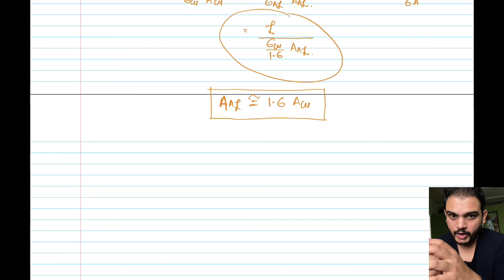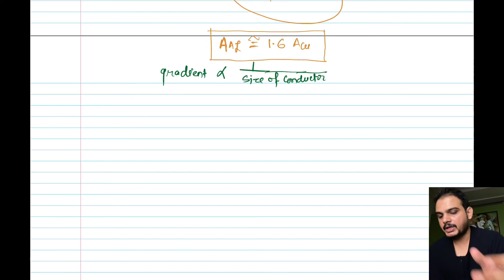This is advantageous because, as I said, gradient is inversely proportional to the size of the conductor. So if the size of the conductor is more, as in our case aluminum will have more cross section area than copper, its gradient decreases. The gradient at the surface of the aluminum conductor gets decreased, so the chances of occurrence of corona will get decreased if we use aluminum over copper for the same operating voltage.